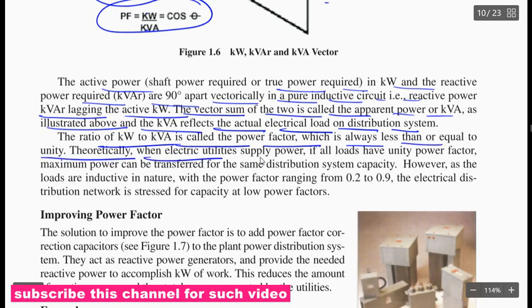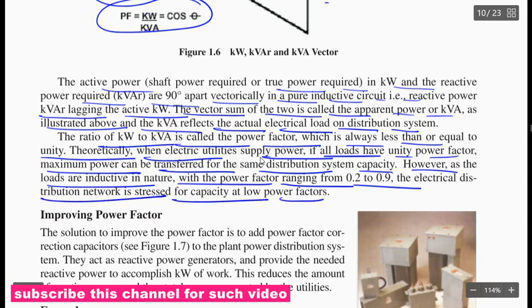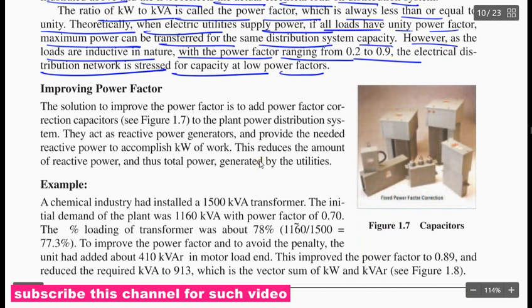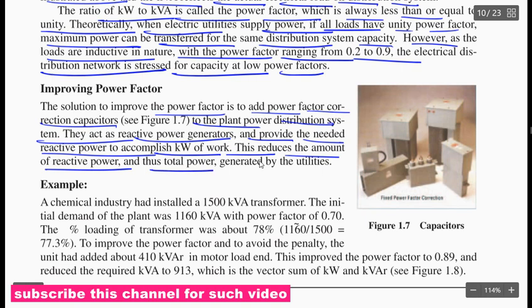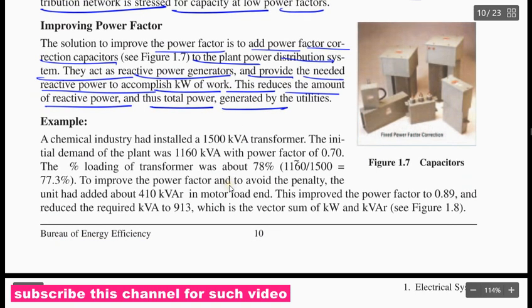Theoretically, when the electrical utility supplies power, all loads would have unity power factor, and maximum power could be transferred from the same distribution system capacity. However, loads are inductive in nature, with the power factor ranging from 0.2 to 0.9. The electrical distribution network is stretched for the capacity because of low power factor. Improving power factor: the solution to improve the power factor is to add power factor correction capacitors to the plant distribution system. These act as reactive power generators and provide the needed reactive power to accomplish kilowatt of work. This reduces the amount of reactive power and thus the total power generated by the utility.